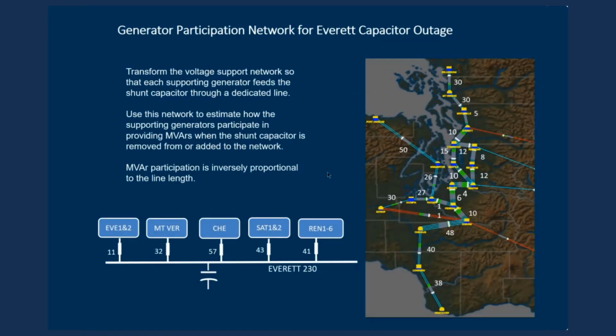The other thing that we can do is we can use that voltage support network and transform it into an equivalent network where each one of these generators is feeding the capacitor through a dedicated line, and the lines have different lengths. And what will happen is that if we trip this capacitor online, each one of these generators will pick up the megavars of that capacitor inversely proportional to the line length. So we call that the generator participation network.